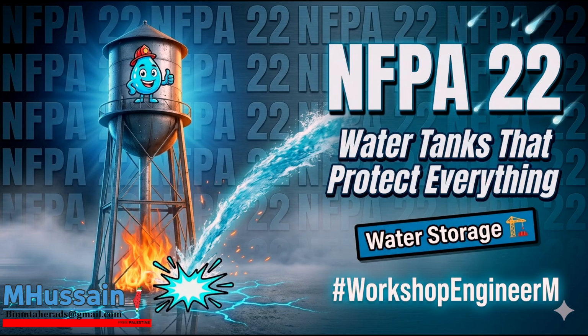So if a fire breaks out at the base of the tower, say, a pallet storage fire in a loading dock, or a fuel spill from a vehicle, and those steel legs reach 1,000 degrees, the columns will buckle under the immense vertical load. It will be a catastrophic structural collapse. You instantly lose your entire primary water supply, completely neutralizing your fire protection system right when it is needed most. Not to mention, dropping 1 million pounds of steel and water onto the facility creates a massive lethal secondary disaster for the building occupants and the first responders.